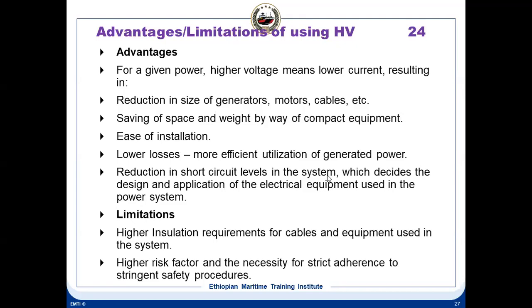So as I told you, a higher voltage gives lower current for a given power. That will make the current reduce, copper loss reduces, the size reduces, cost reduces, space reduces. The main advantage is reduction in short circuit levels. So your protective systems need not be very high current rated. That means for a breaker, you can reduce the current rating drastically, because your current is reduced. Your short circuit levels are reduced.